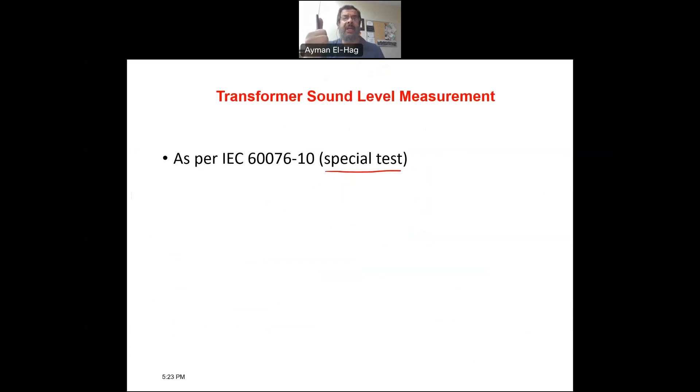So it's not a routine test that you have to do for every single transformer. It's not a type test that you have to do in every design, but this is only you do it as an agreement between the manufacturer and the user of the transformer. Now you measure the sound level coming from the transformer as sound pressure level and there are certain sensors used to measure the level of the noise coming from the transformer.